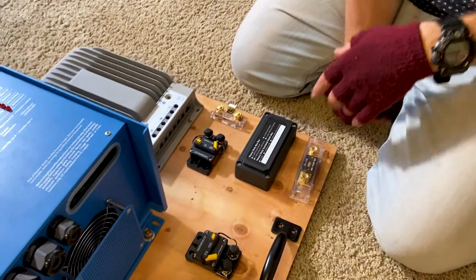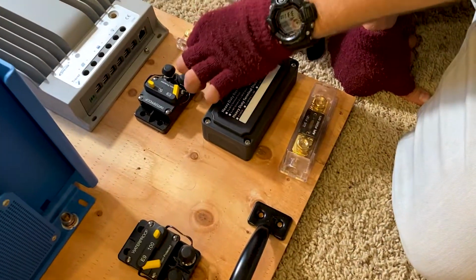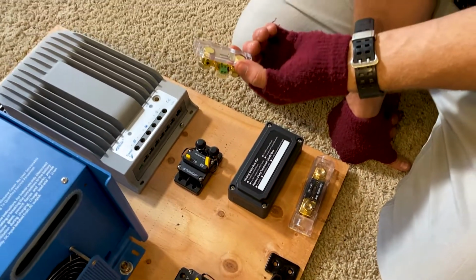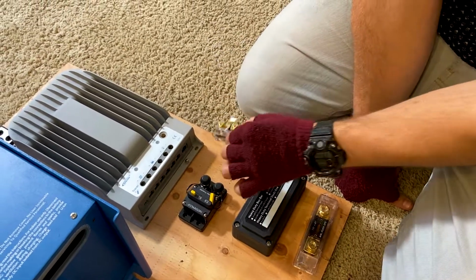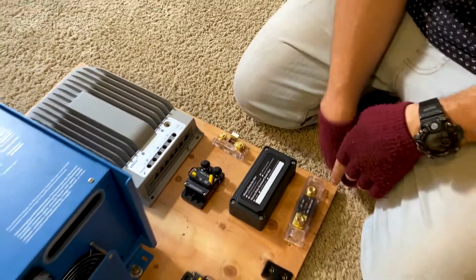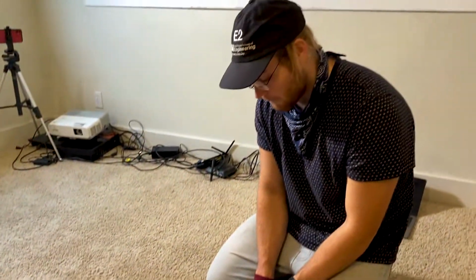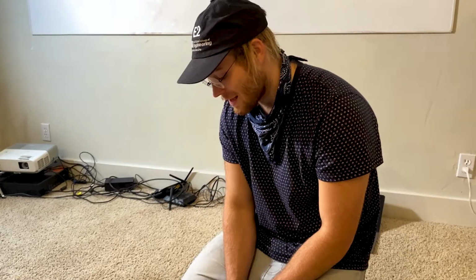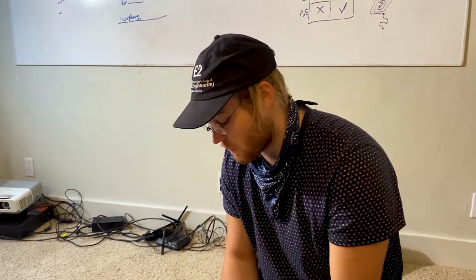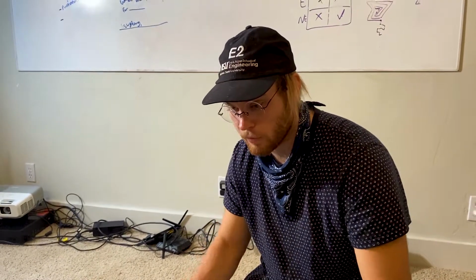Since this is a 40 amp charge controller, 40 times 1.25, we went with a 50 amp circuit breaker. Then the rest of the components: this right here is a shunt, for connecting our battery monitor so we can monitor the voltage in our system. And finally, we've got our main positive fuse, a 300 amp fuse, and our main negative bus bar just for connecting the batteries to the whole system.